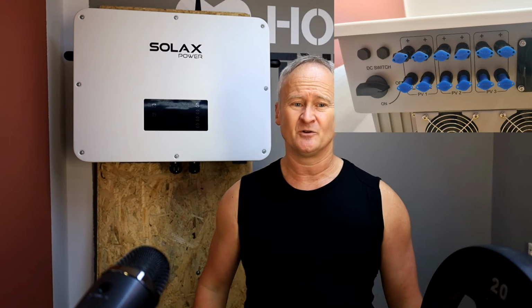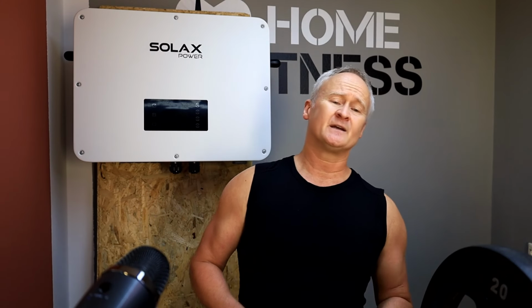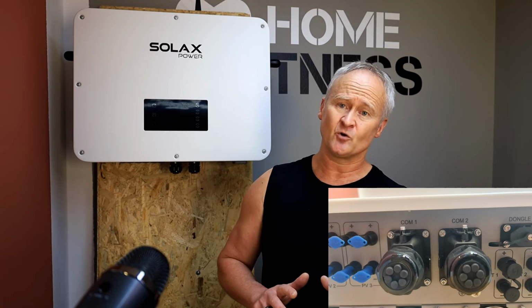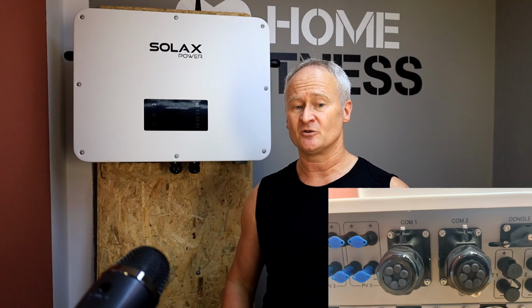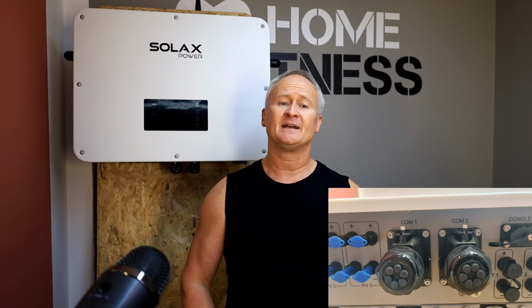As mentioned, there are 3 of them, each with 2 parallel inputs for our PV strings. What's new with the Solax X3 Ultra? We no longer have the usual BMS, CT meter, CAN1, CAN2 connections, and so on, but instead we now have not just one, but actually 2 communication ports, labeled COM1 and COM2. Behind each of these units are the dedicated slots for the RJ45 connectors, providing the essential connections for communication in a parallel installation setup, and also facilitating communication with the 2 possible battery strings or the BMS, which is specifically located behind the COM1 port.